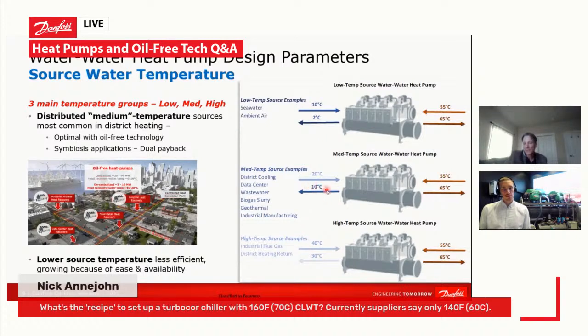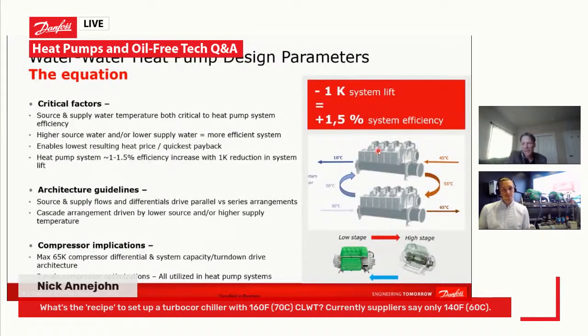The most common that we see is the medium temp. But the architecture that you'll use for a low source water temperature example is much more complicated and is very different from what you'll use for a high temp source example. Related to that, and just to finish the rest of the story, for every 1K that you're decreasing the lift that the overall heat pump plant has to do, you're improving the system efficiency by about 1.5%. So what we try to do is, of course, focus on the higher source water temperature applications, as well as the lower supply water temperature applications, as the optimal for a payback of these systems.